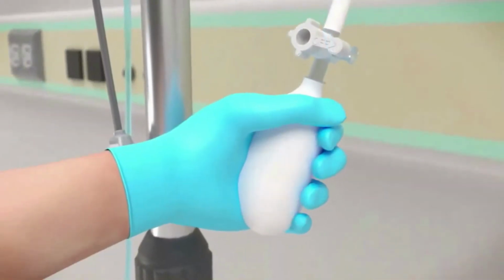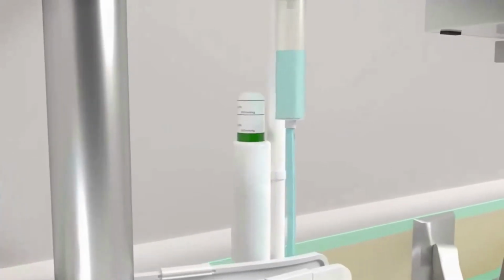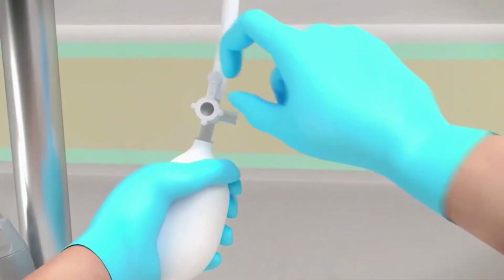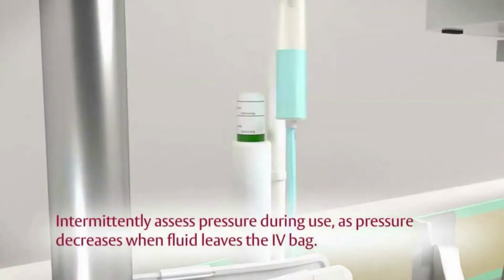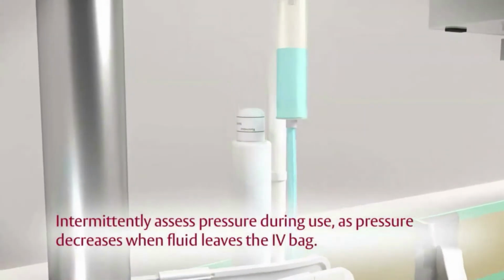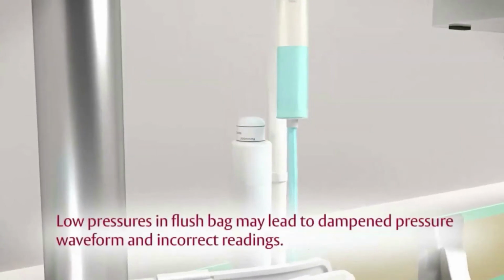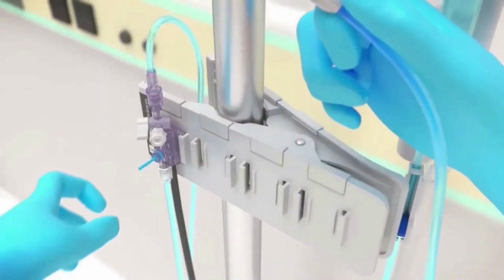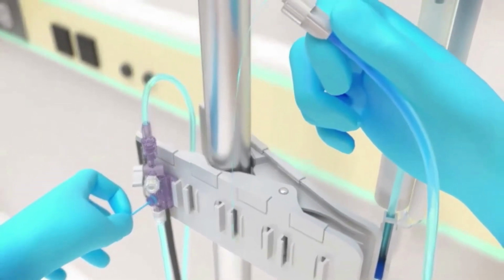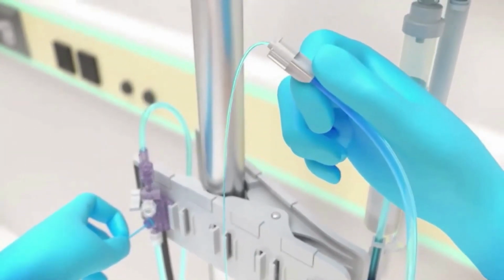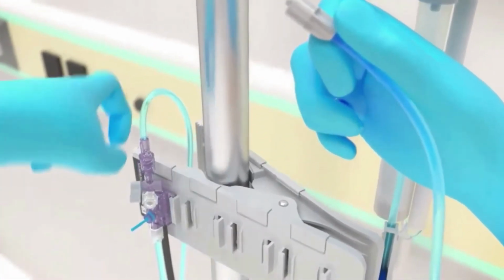Pressurize the IV flush solution bag to 300 millimeters of mercury. Turn stopcock toward the pressure bag to lock off air pressure. Intermittently assess pressure during use, as pressure decreases when fluid leaves the IV bag. Low pressures in flush bag may lead to dampened pressure waveform and incorrect readings. Pull the snap tab to flush the system under pressure, while tapping on the tubing and stopcocks to remove any residual bubbles.